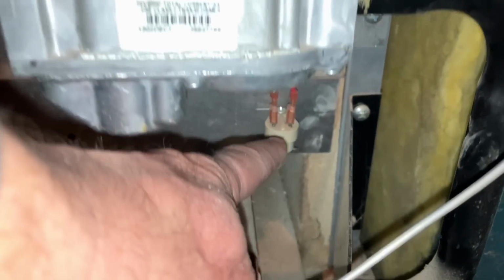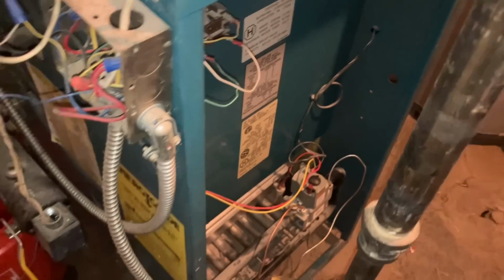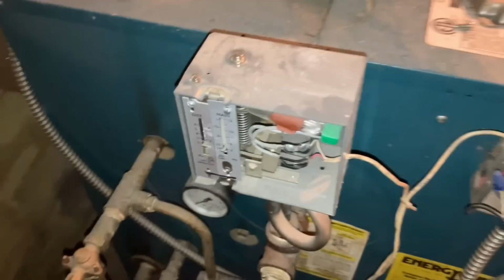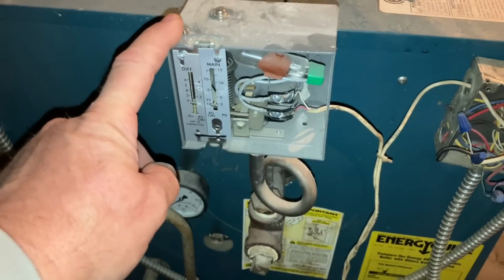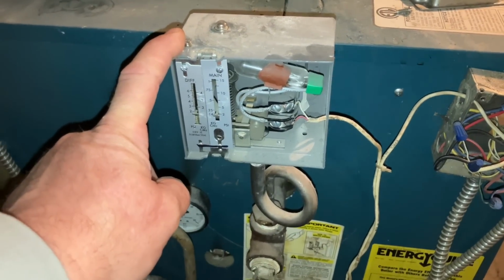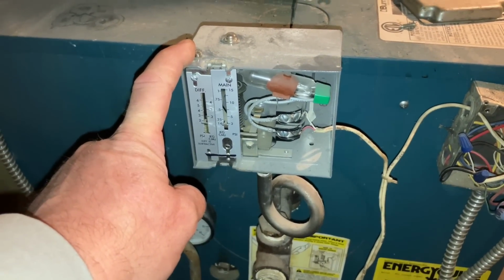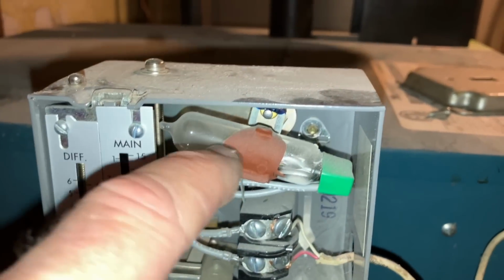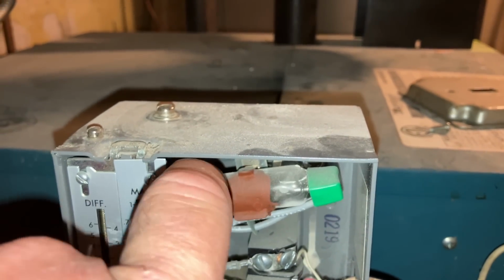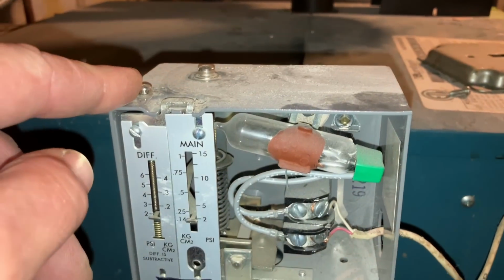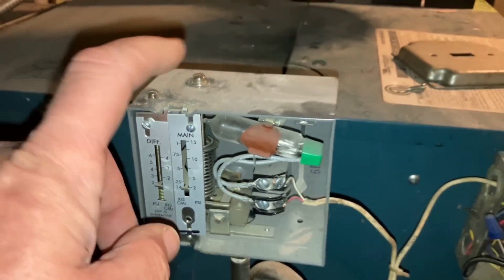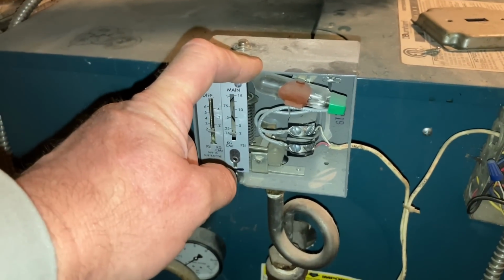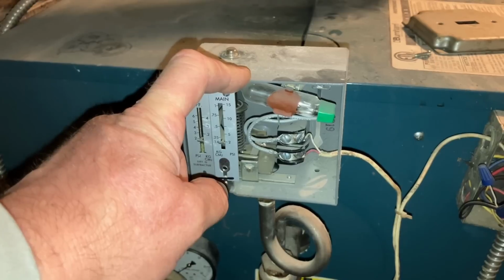There's a flame rollout switch, which is a ceramic disc that burns out at temperature, and it's not resettable, so once it dies, you need to replace it, figuring out what caused it to die. We have a pressure control here. This controls pressure in the system. This is a primary safety device. This one has that little mercury bulb in there. You're not going to see it anymore because they wanted to outlaw mercury because they said it was bad for us, but nothing controls steam pressure or temperature better than mercury does.